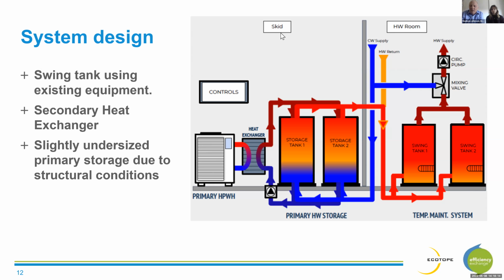And then the other thing I wanted to mention is that in this project, we were limited on the amount of storage that we could add in the primary storage tanks because of structural considerations for the roof that we put this on. So it's actually slightly undersized from what we normally would have, or what we initially wanted to install in this building. And so our ability to do the load shifting is kind of a worst case scenario, and we're still able to do quite a bit of load shifting with what is otherwise a potentially slightly undersized heat pump and storage system.